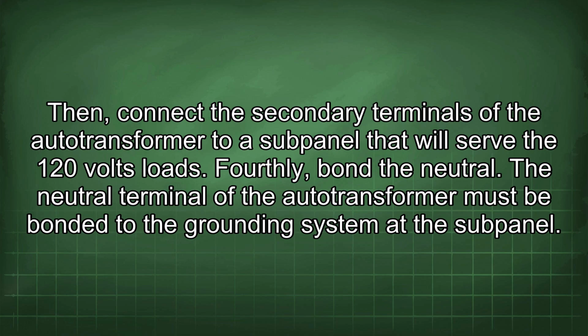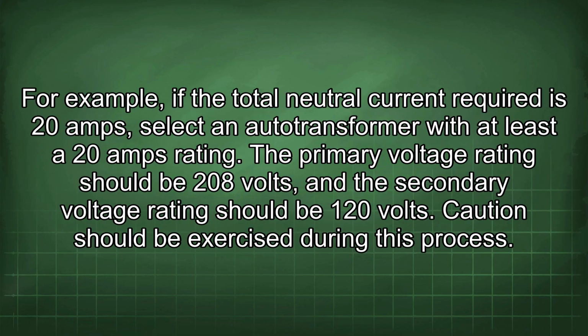Fourthly, bond the neutral. The neutral terminal of the autotransformer must be bonded to the grounding system at the subpanel. For example, if the total neutral current required is 20 amps, select an autotransformer with at least a 20 amp rating. The primary voltage rating should be 208 volts, and the secondary voltage rating should be 120 volts.